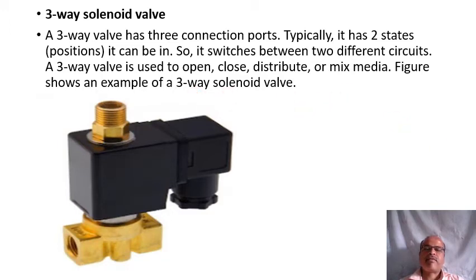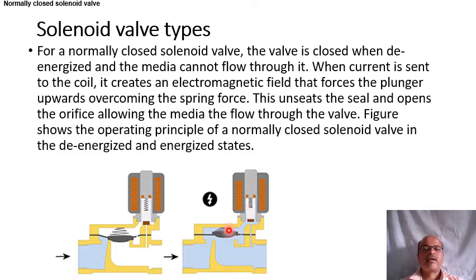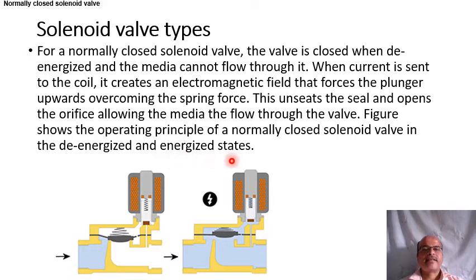For a normally closed solenoid valve, the valve is closed when de-energized and the media cannot flow through it. When current is sent to the coil, it creates an electromagnetic field that forces the plunger upward, overcoming the spring force. This unseats the seal and opens the orifice, allowing the media to flow through the valve.